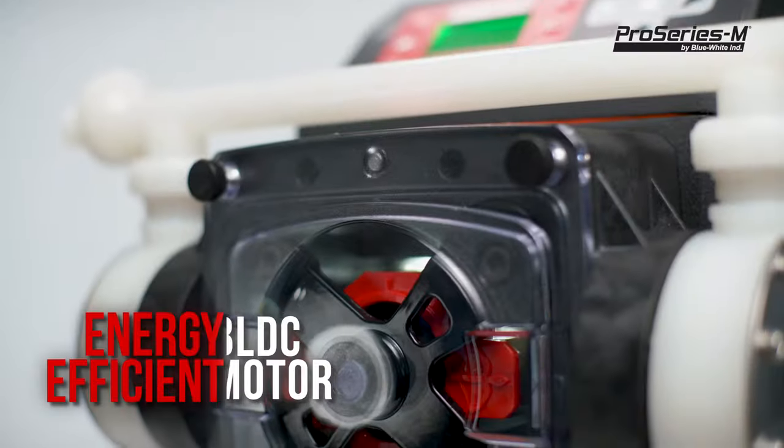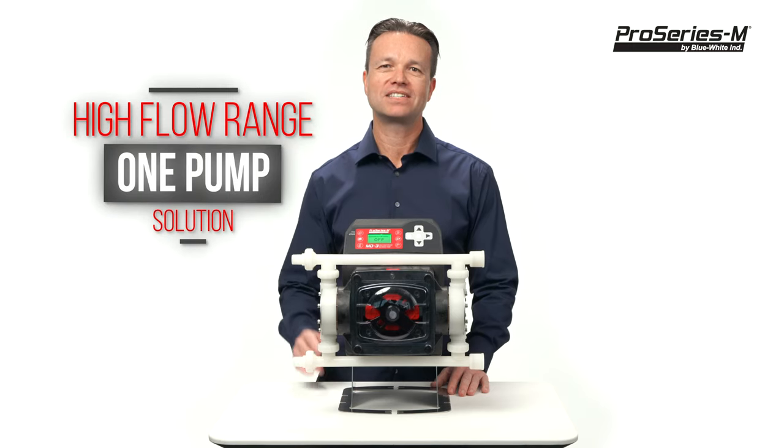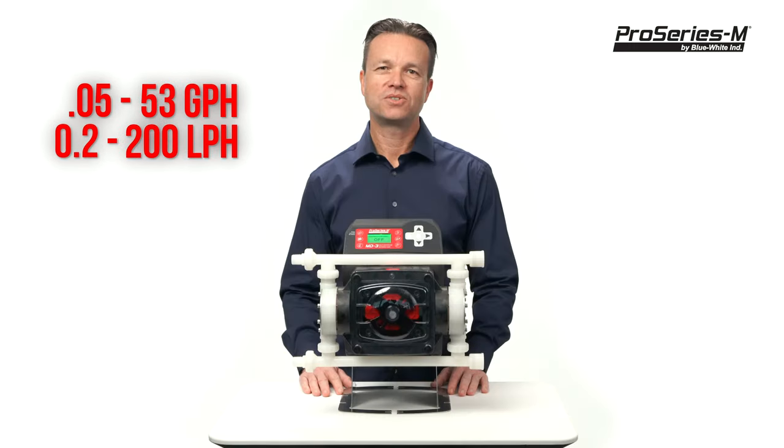The MD3 has an energy efficient BLDC motor, which enables an incredible turndown ratio. The pump's large flow range means you can standardize on one pump for most of your chemical feed needs. The flow range is from 0.05 to 53 gallons per hour, or 0.2 to 200 liters per hour.